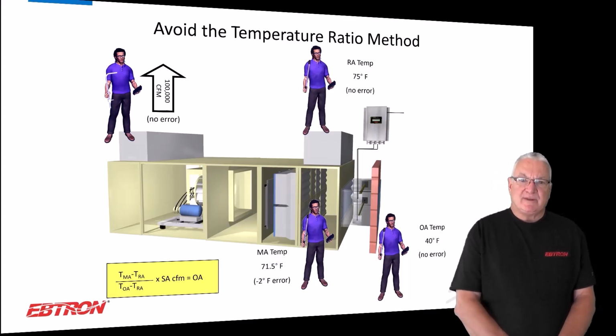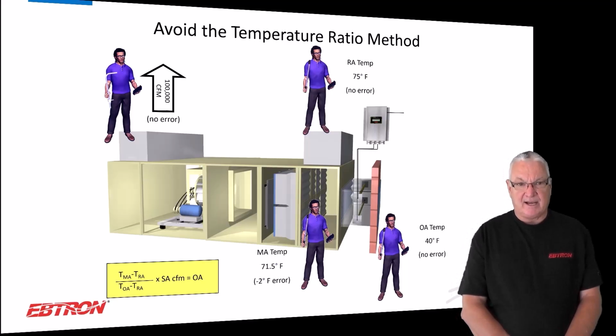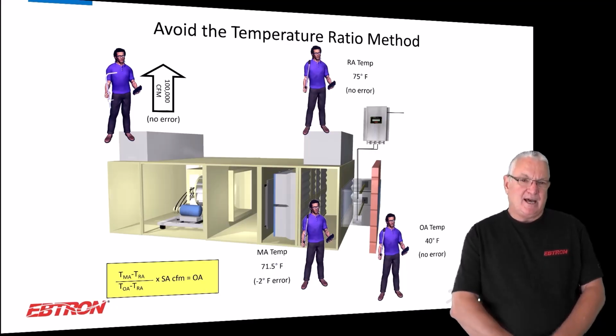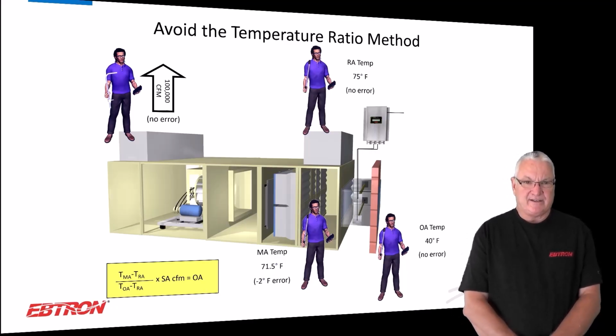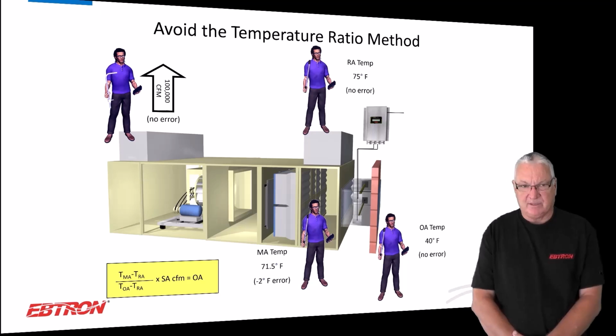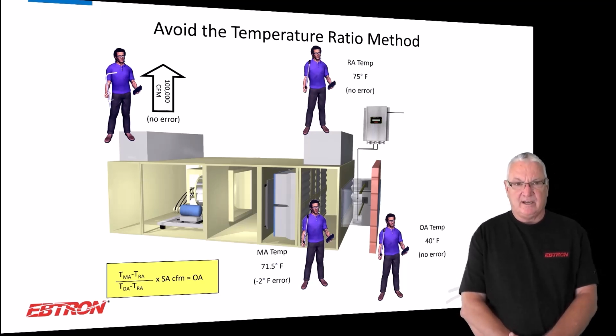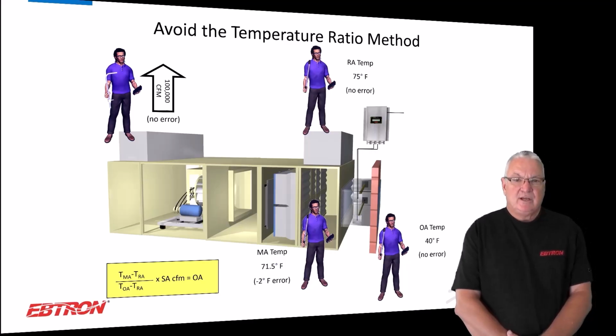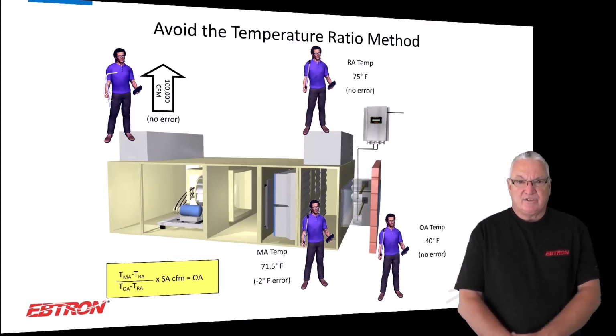So I'm calculating everything with those measured temperatures, and then I'm looking at the supply flow rate, and I like to pick nice easy numbers, so 100,000. It doesn't matter what you use on the supply flows, it can look the same way. 100,000 CFM of supply air, again no error, which is not reasonable. It's probably 3 to 10% depending on what you're measuring it with. But let's just say there was no error.